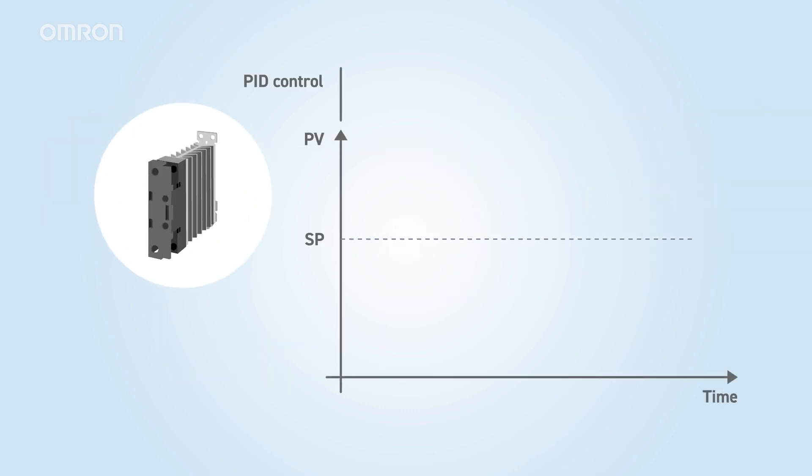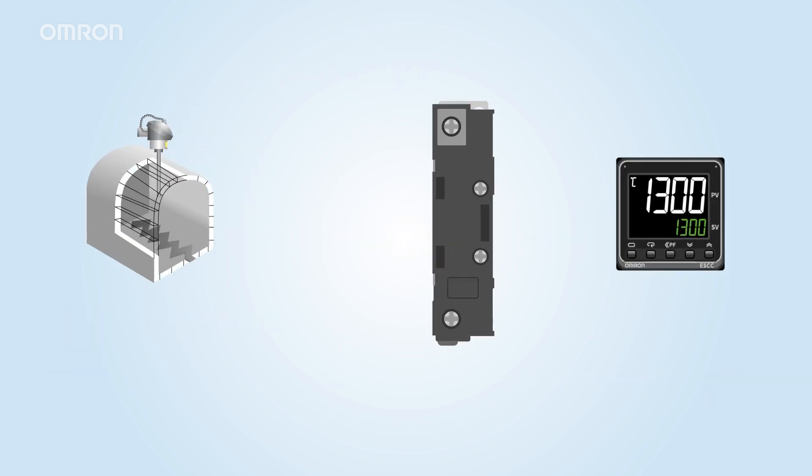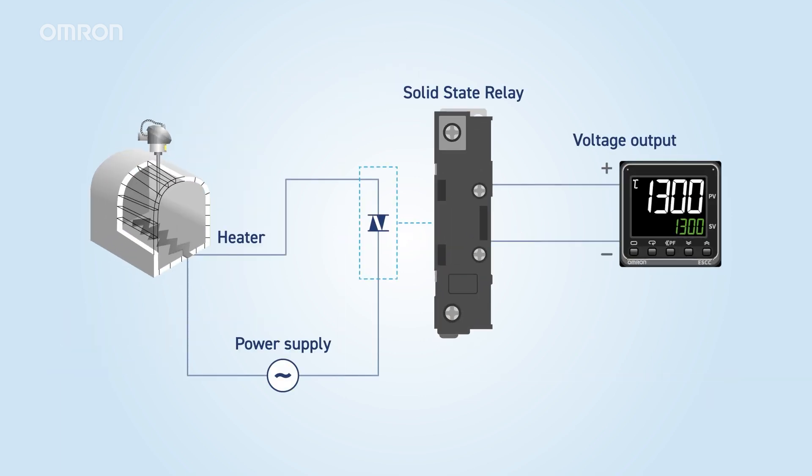Solid-state relays use semiconductor elements. Since they have no physical contacts, there is no lifespan due to the number of open-closed cycles, they can frequently switch the heater on and off, making them suitable for PID control. However, they have higher power losses and require larger sizes for heat dissipation. Click here for the details about our SSRs. When using SSR, a temperature controller with a voltage output is used. The SSR turns the heater on as long as it receives voltage from the temperature controller.